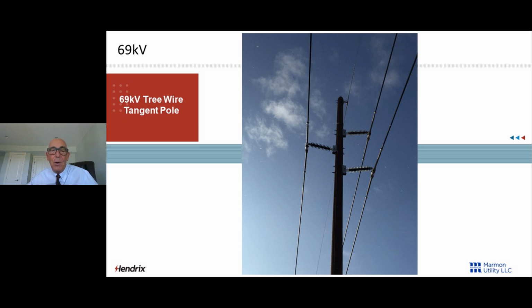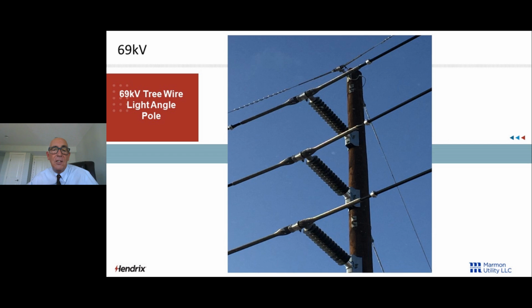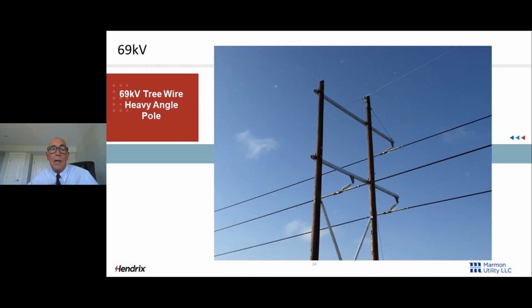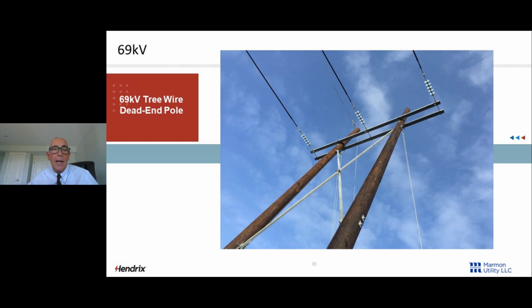This is what a tangent pole looks like. We're basically using line post insulators with suspension clamps and IPCs to hold those phase conductors. That takes a little bit of explanation. Here's a light angle pole. Here's a heavy angle pole. They put it on an H-frame, but they still had that super compact configuration. And a dead end pole: since we're stripping it, we had to bring those phases out back to bare wire dimensions.